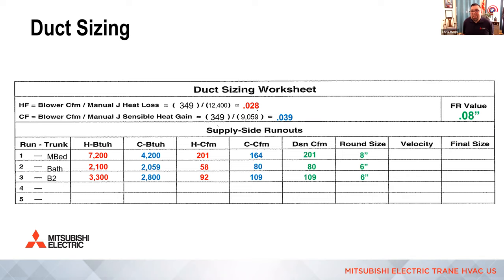Andy asked, and Andy, I happen to know you, been a long time. How does the rule of thumb for velocity change in a super insulated or passive house with very low heat losses? The design changes, but your velocity doesn't change, right? So you still don't want a noisy duct system. What's going to end up happening is hopefully that system is going to run at partial load much more often. So it's going to ramp down.